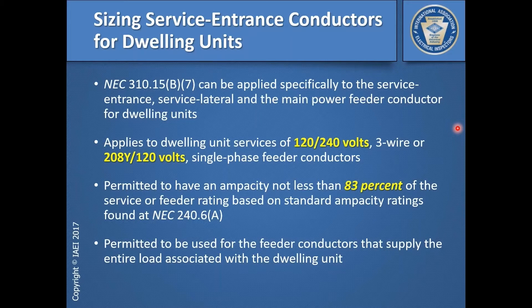It applies to dwelling unit services: 120/240-volt or 208/120-volt single-phase services or feeders. For the 2017 code, what you're basically looking at is doing an 83% load calculation on the ampacities that you would get from the most-used table in the National Electrical Code, 310.15(B)(16).